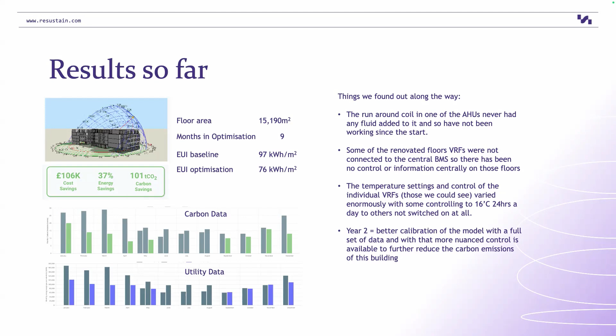And the things we found out along the way is that various things were missed over time. The runaround coil didn't have fluid added to it, so it's never been working. Some of the systems weren't connected up to the BMS. There's a lot of strange VRF controls going on - some of them are on 24 hours a day at 16 degrees, conditioning space at 16 degrees. So with the full set of BMS data over a year, you can start nuancing those controls even further as we go.